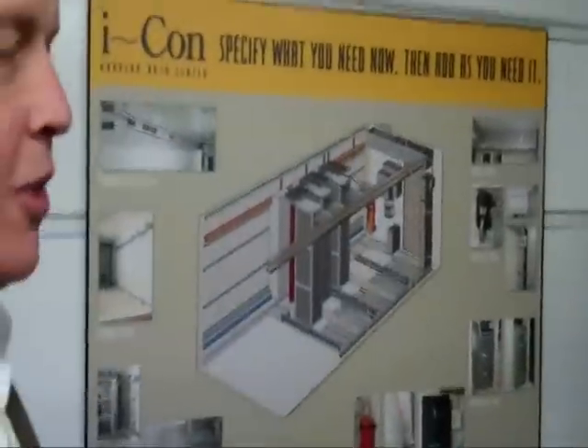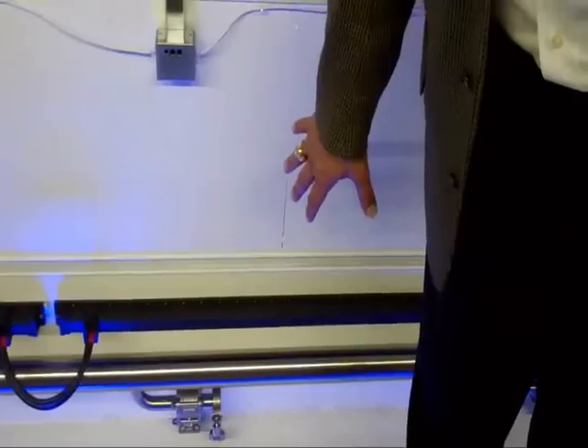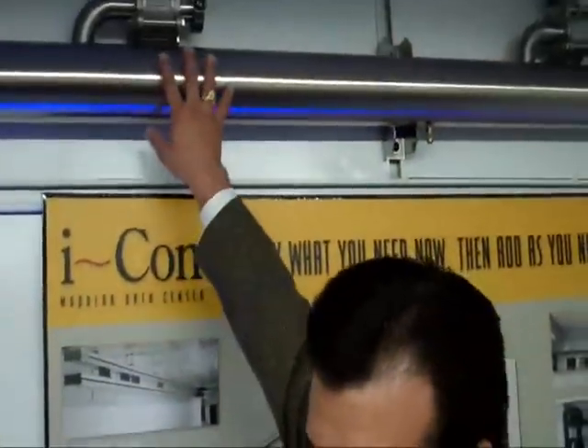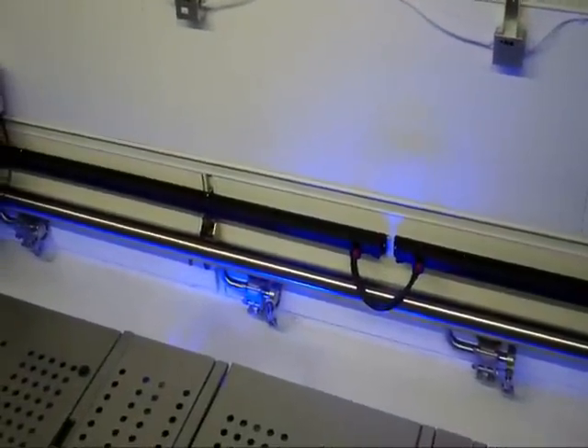Tell us about the cooling — you've got some piping here. I'll let our CTO, Tim, handle that. Tim Cortez, CTO of VDI. The system is refrigerant-based inside the container. We have chilled water coming external to the container, but no actual chilled water inside. We have a manifold system: on the bottom, a supply manifold filled with liquid refrigerant R134A; on top, a slightly larger manifold that returns spare liquid refrigerant and vapor from each rack back to the main condenser at the other end. The system is modular — at each rack position we have a valve connection for the supply and return line, where you tie in the refrigerant pump, the evaporator, and the other cooling aspects directly associated with each rack.